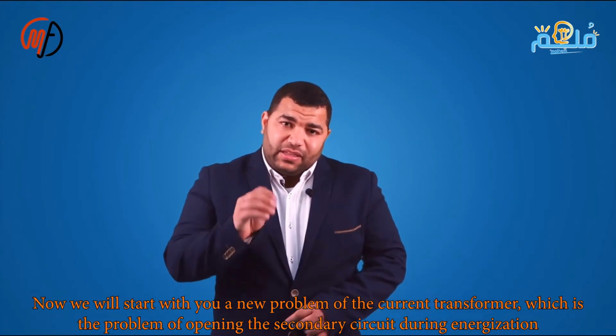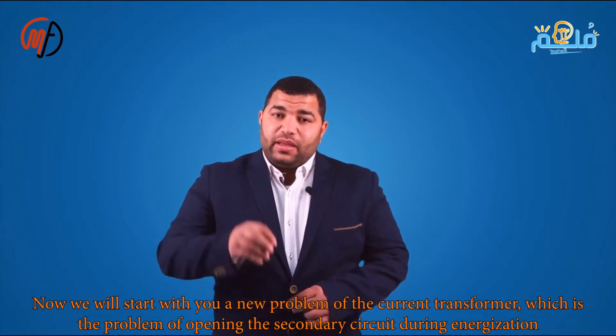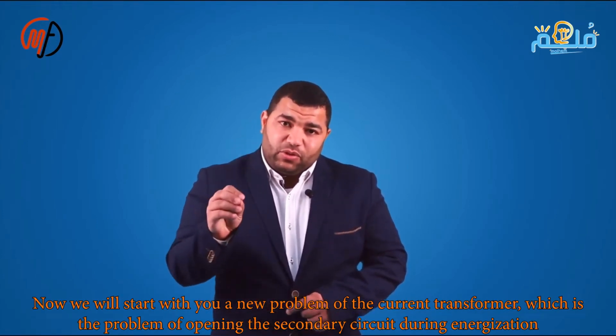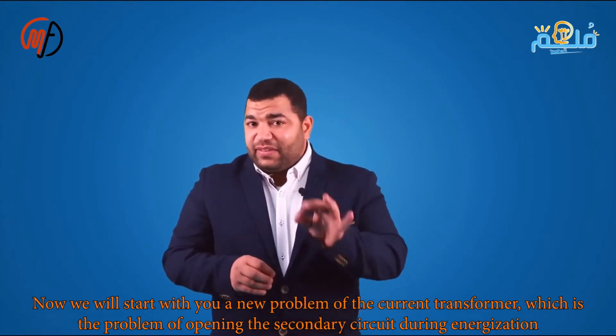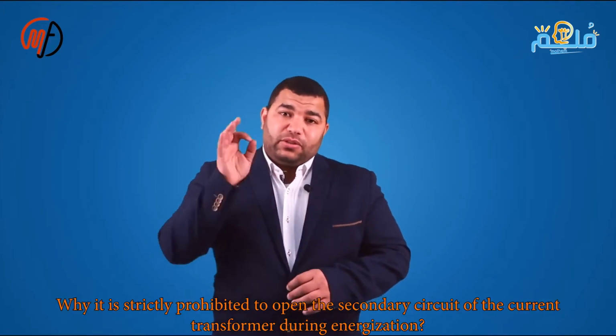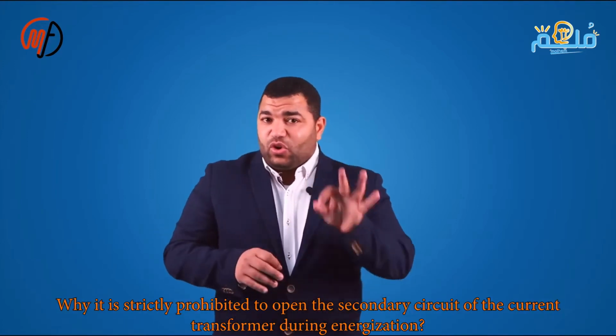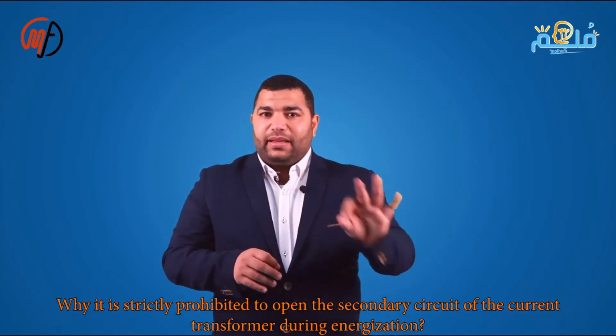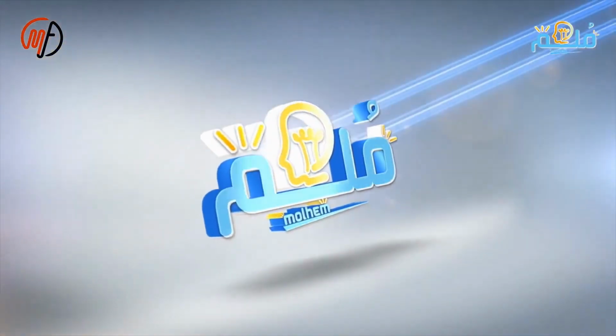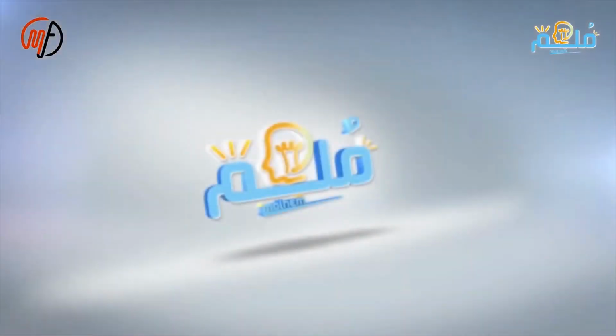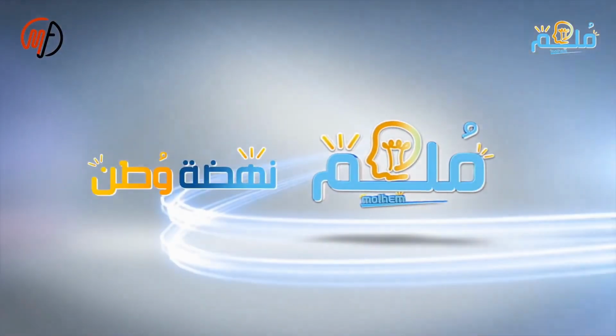Opening the CT secondary circuit while energized is strictly prohibited. When primary current flows through the CT, it creates a magnetic field. This field generates a force pushing flux into the core. Flux flows in the core, intersects with the secondary winding, creating voltage, generating current when a load is connected. This current creates a field opposing the original, reducing its value. If the circuit opens, no opposing force counters the original field, concentrating current in the core and increasing voltage across the terminals.